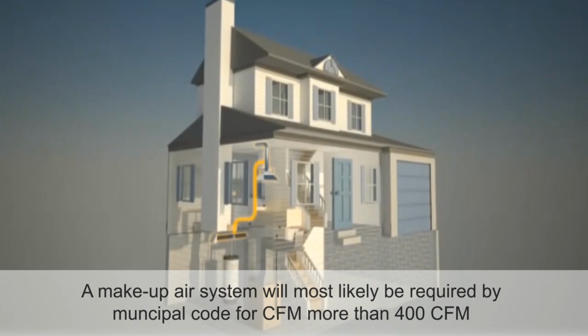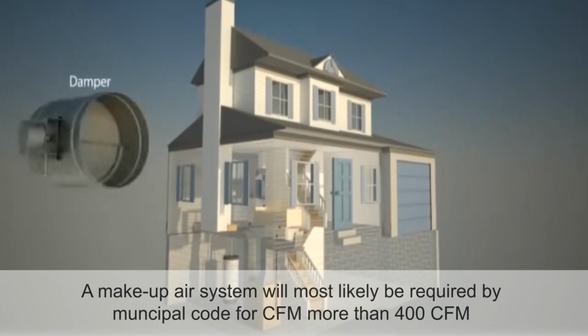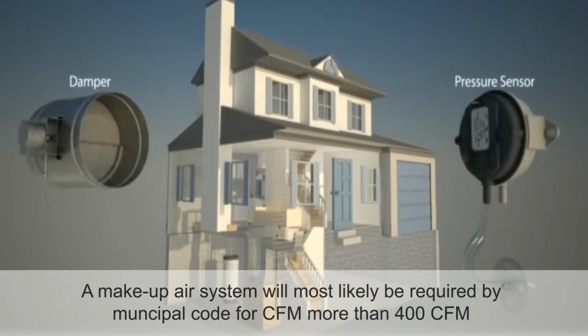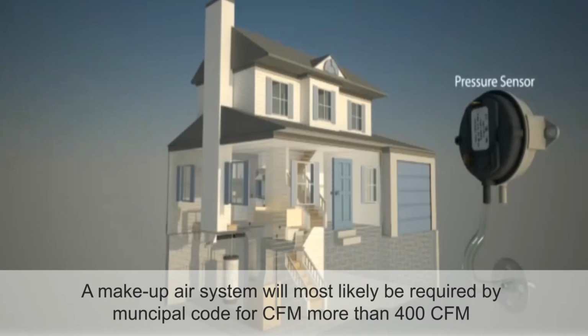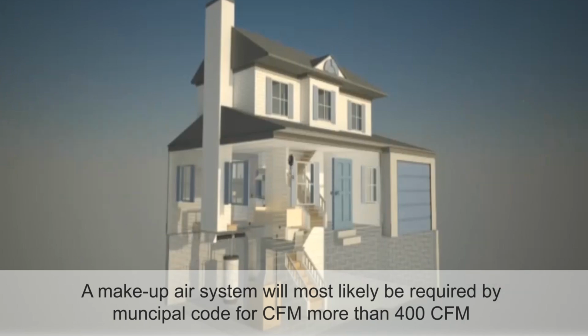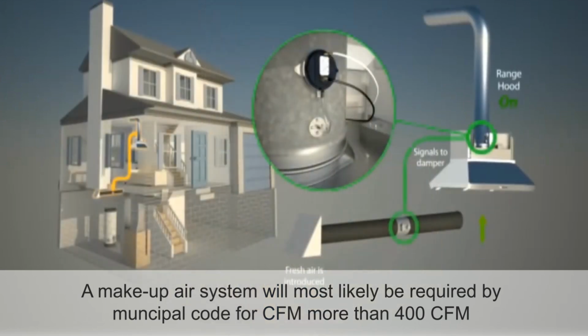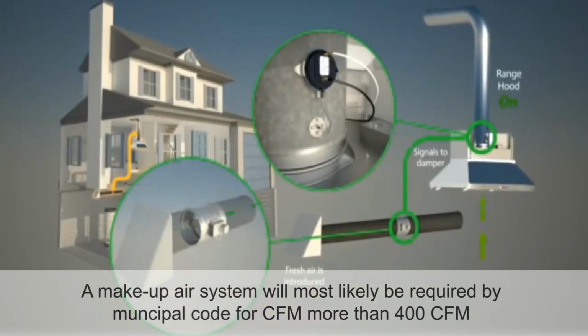These systems typically include an interlocked makeup damper. These types of systems include a damper assembly with an exhaust flow sensor that provides a synchronized system. Some systems only require using low voltage wiring that connects the sensor and the makeup damper. The system delivers fresh air in a controlled manner, which improves indoor air quality through balanced ventilation. It's important for the customer to understand that if they are unsure of their range hood CFM requirements for more than 400 CFM, they need to check with their local municipal code officials.